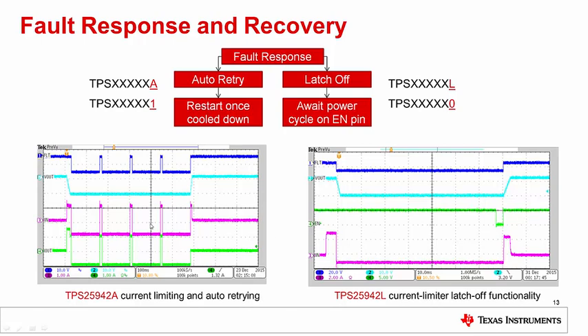On the other hand, an auto retry device continues to power cycle itself until the fault is cleared. The left side image shows how TPS25942A resumes normal operation when the short circuit fault is cleared. The last digit of the part number indicates the type of device. A and 1 correspond to the auto retry version and L and 0 correspond to the latched version.